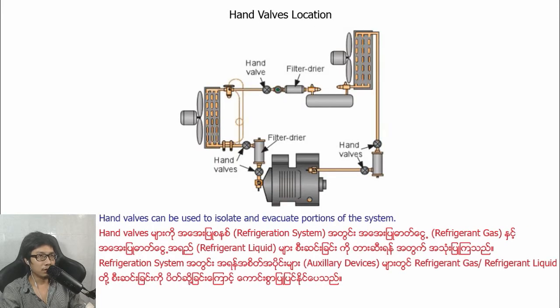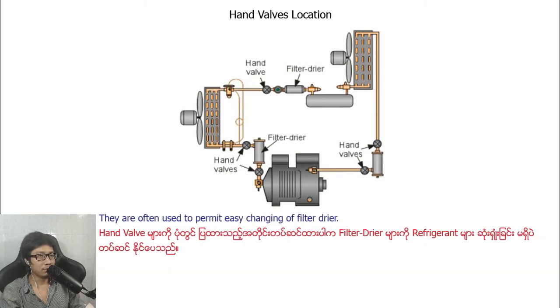Hand valve location. Hand valves can be used to isolate and evacuate a portion of the system. They are often used to permit easy changing of the filter dryer.